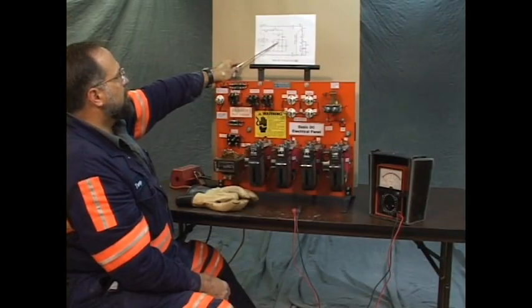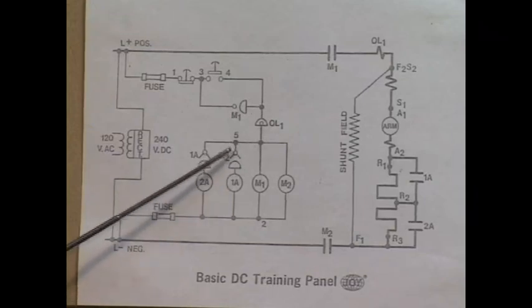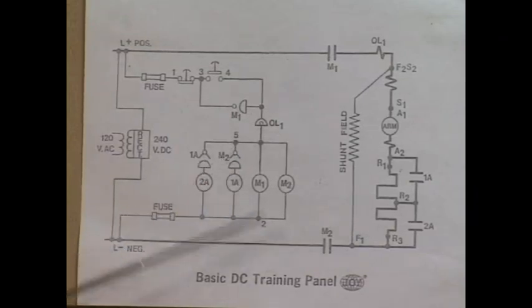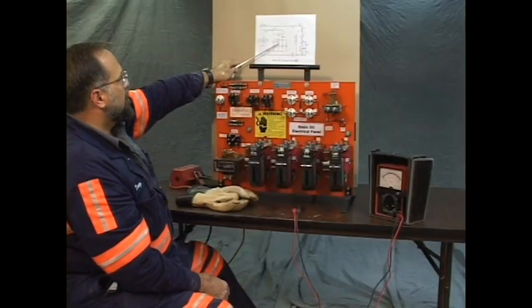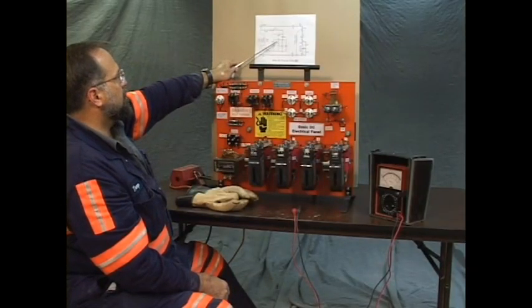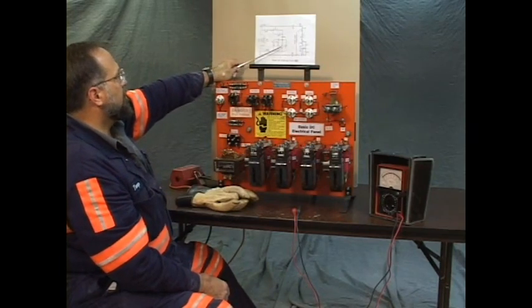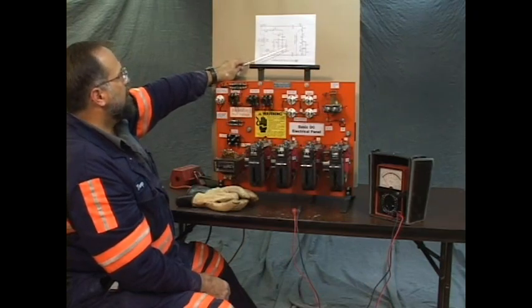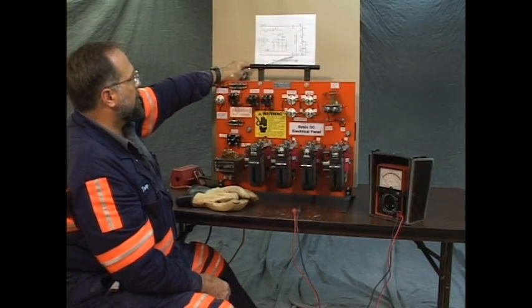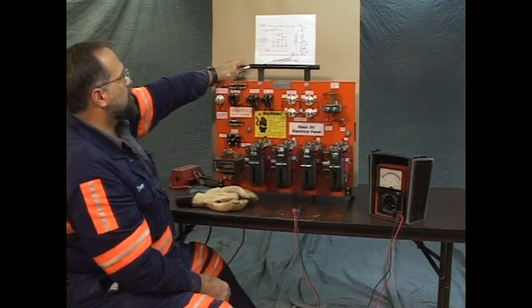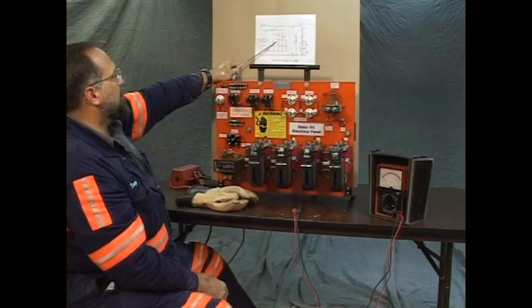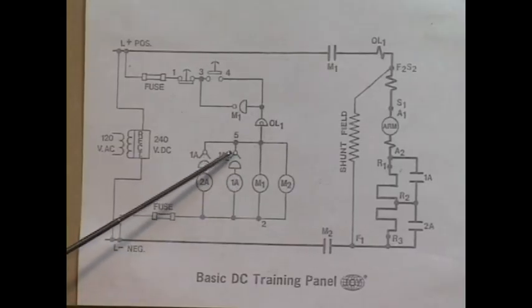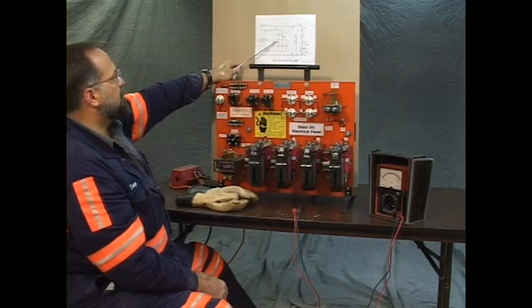Note also that there's a timing device, a timing mercury tube, on 1A's circuit and 2A's coil circuit. The 1A coil is timed by a mercury tube attached as an auxiliary to the M2 contactor. When M2 becomes a magnet, it has the effect of closing these tips and providing a path for the negative for the power circuit, as well as timing this mercury tube. When the symbol on the print is shown like this with the two little outriggers on the stationary part of this, that means it's a timed mercury tube.